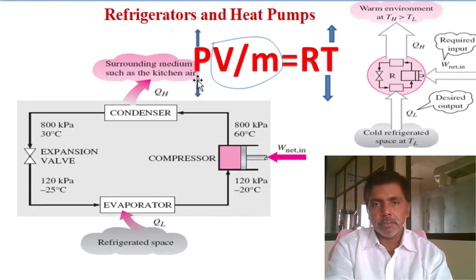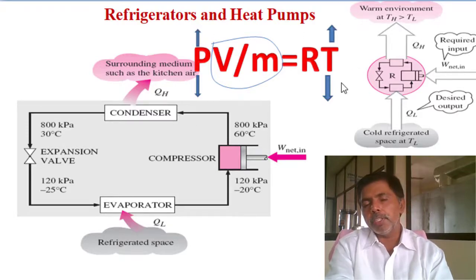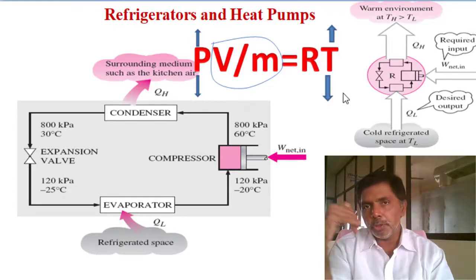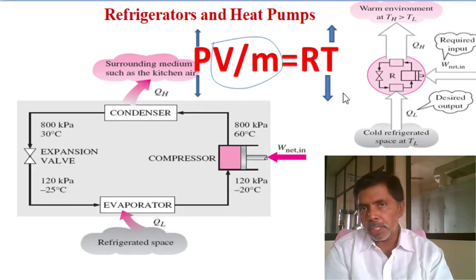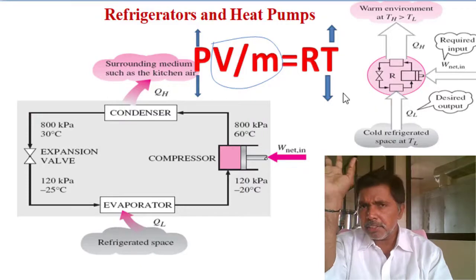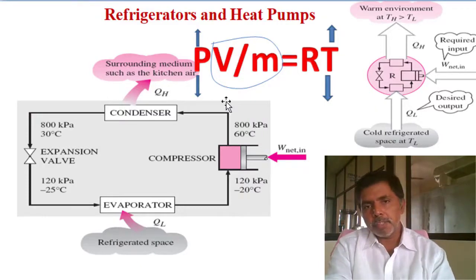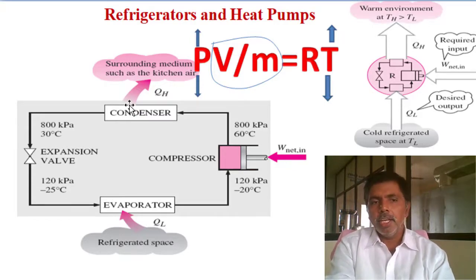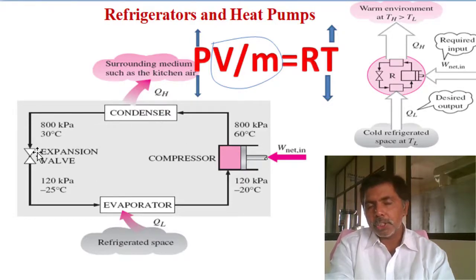Since V/M is constant, increasing pressure means temperature will increase, and decreasing pressure means temperature will decrease. So we increase pressure when we want to reject heat, and decrease pressure when we want to absorb heat. That is the basic principle. The commercially available vapor compression refrigeration cycle consists of a compressor, condenser, expansion valve or throttling valve, and an evaporator.